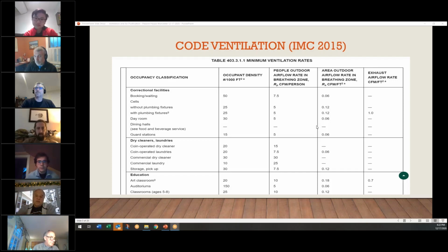The only other interesting thing when you use this table is you look at your exhaust airflow rate. For an art classroom, they need 0.7 CFM per square foot of exhaust. So that might actually override your outdoor air requirements, where you might need more than just the 10 CFM a person. You might also need to make up that amount of exhaust, which would dictate your higher fresh air level, unless you're pulling it from a plenum or some other source to get that exhaust rate. But that's another variable that comes into play. And this is a few page document. This is just a piece of it that shows how you would determine your outside air. If we go to the next slide.